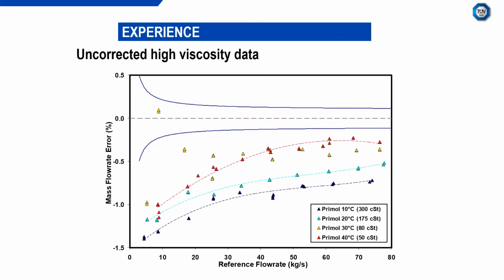We now operated uncorrected with a high viscosity fluid. This time the trade name of this fluid is Primol. We operated again at 10 to 40 degrees Celsius, and this gave us a viscosity range between 50 and 300 centistokes. And you can see that there's a definite Reynolds number or high viscosity effect here. However, we've also overlapped a curve for each temperature and viscosity. So for Primol, you can see the data with a blue polynomial through it. We've got a lighter blue, or teal, one for the 20 degrees Celsius. The yellow one we didn't put a curve fit through because there does appear to be a bit of separation, whether this is zero effects affecting the 30 degree data, but it wasn't quite as robust as the other temperatures.